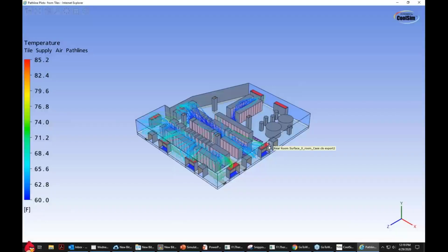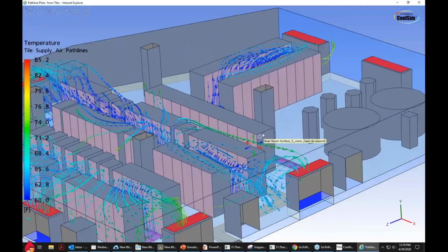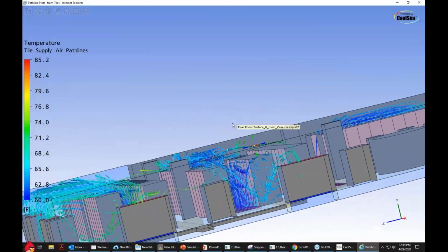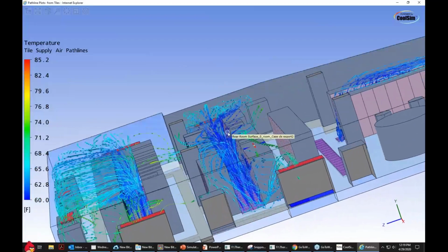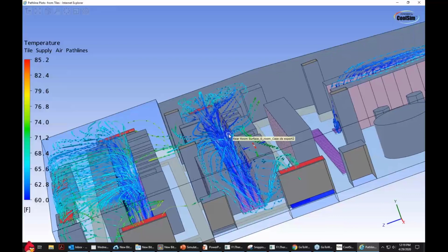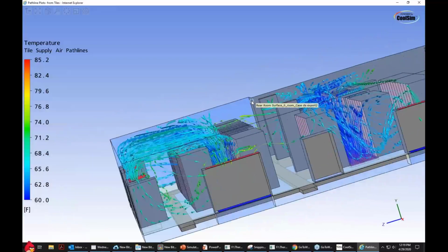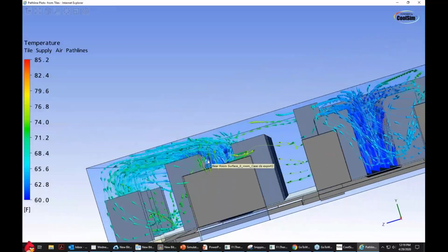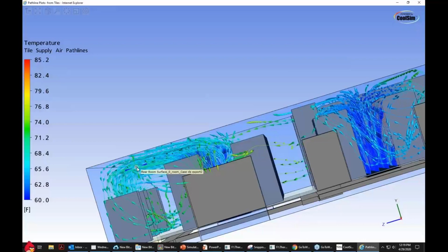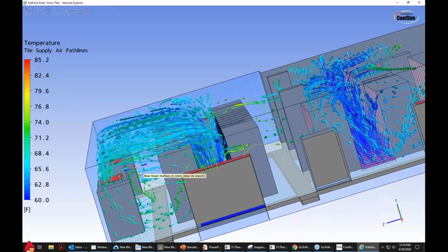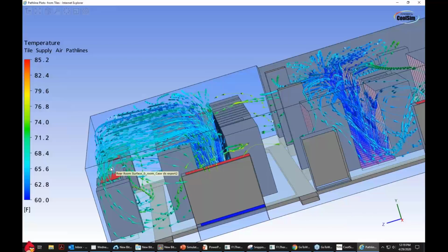There's a couple things about this data center that are a mess. This is a 3D representation of the air coming out of the tiles. This is what comes out of the CFD modeler. And you see an awful lot of recirculation going on right here. So right here, the air is coming up and back into the heat exchangers. Now this is a bad thing because we're cooling off those returns. You shouldn't see those at all here.